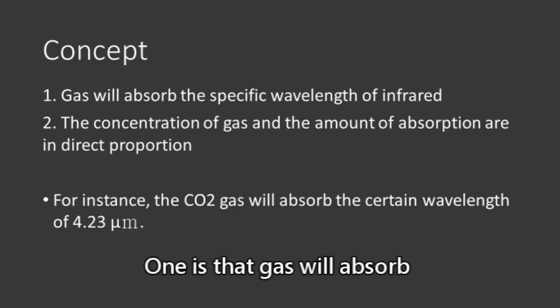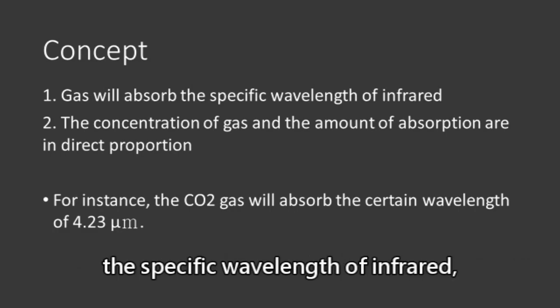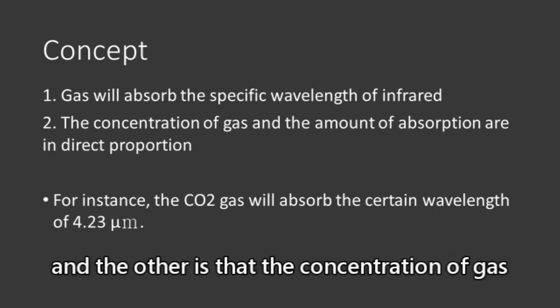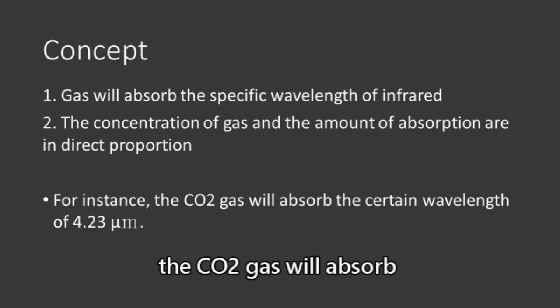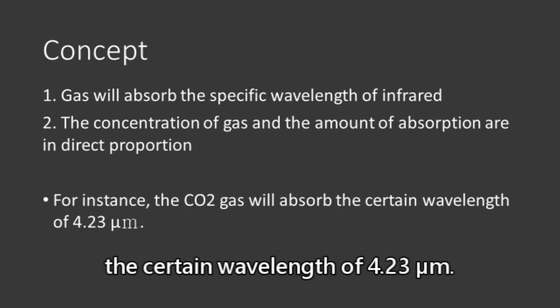One is that gas will absorb the specific wavelength of infrared. And the other is that the concentration of gas and the amount of absorption are in direct proportion. For instance, the CO2 gas will absorb the certain wavelength of 4.23 micrometers.